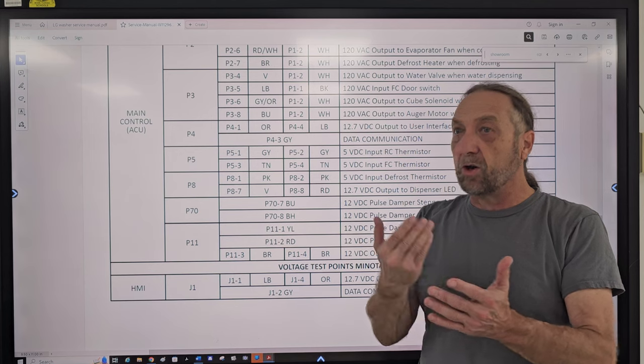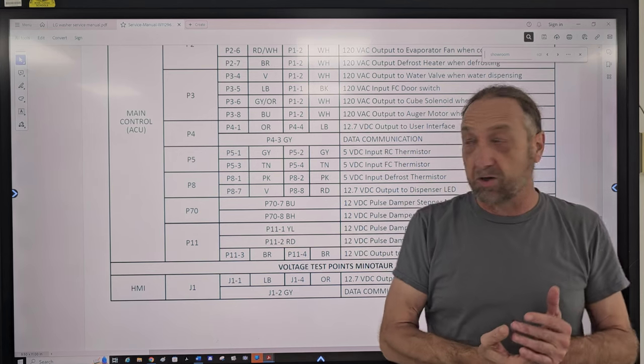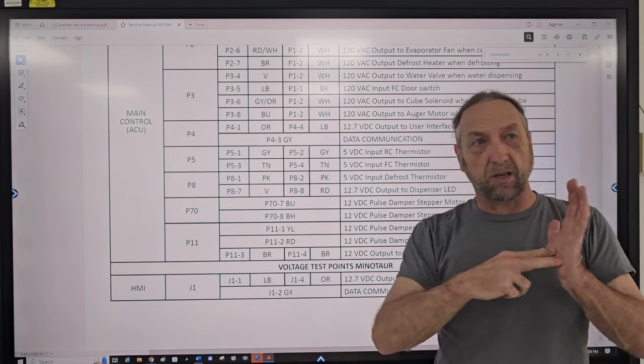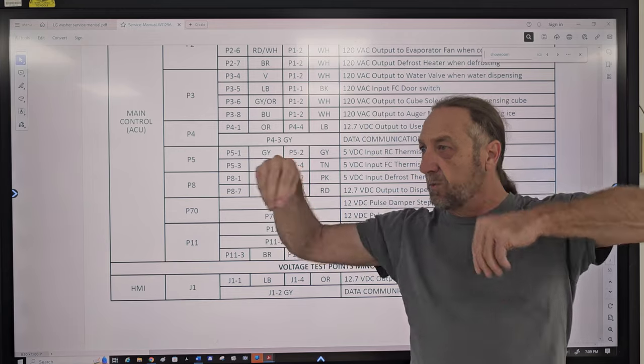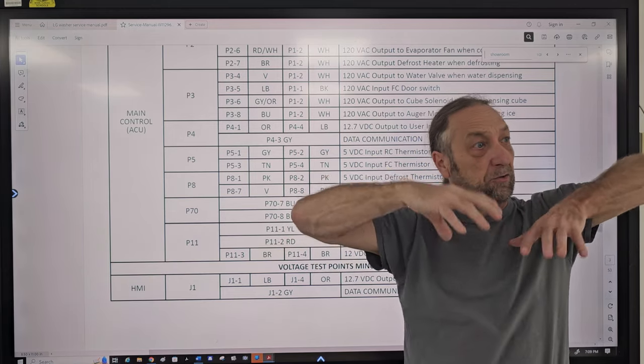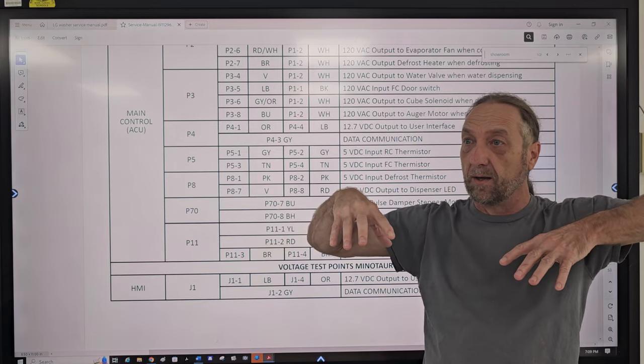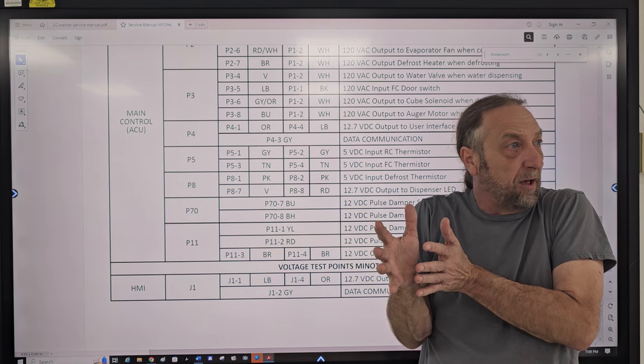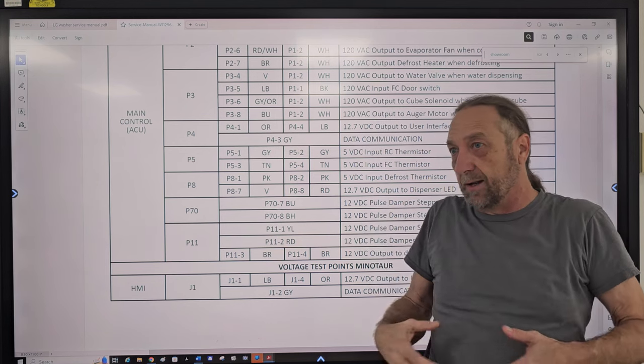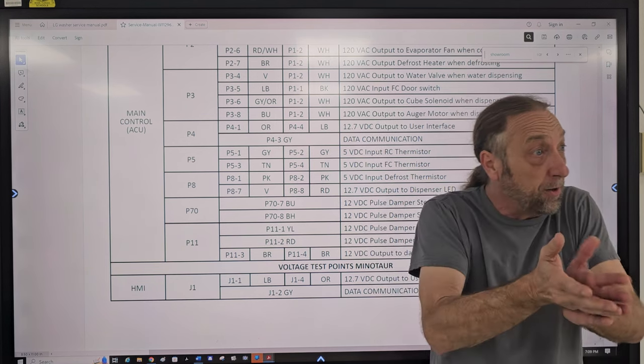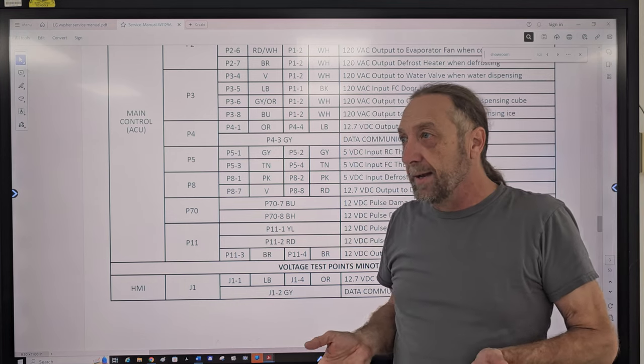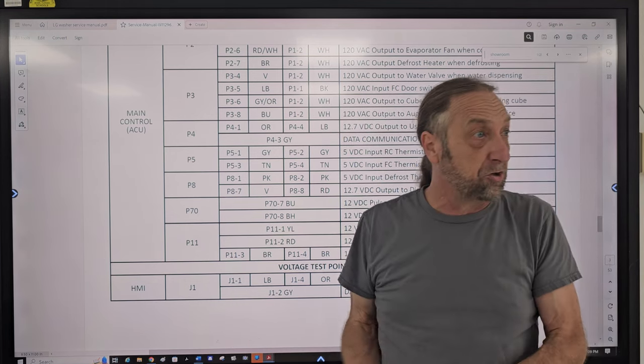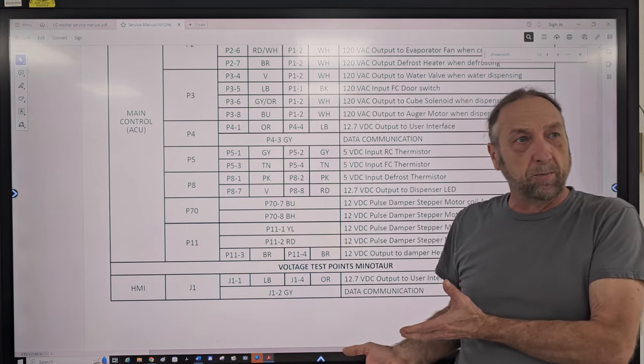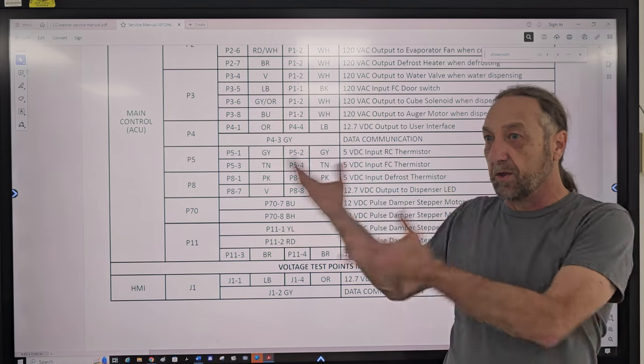But if I'm getting the error code of a bad thermistor, remember, a thermistor plugs into a board, but a board has resistors and capacitors and diodes to create that circuitry. The board could have a fault itself, it could have cockroaches or moisture on it, shorting a little resistor on the board. Now all of a sudden the board gives a thermistor error, and it's not an error with the thermistor, it's an error with the board.